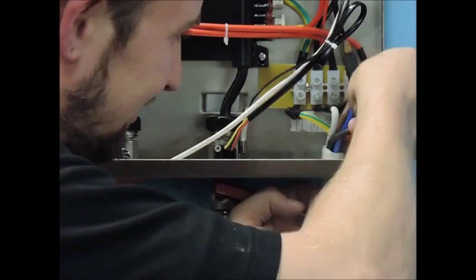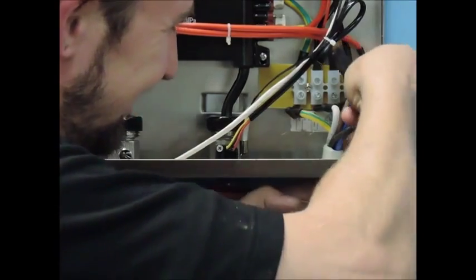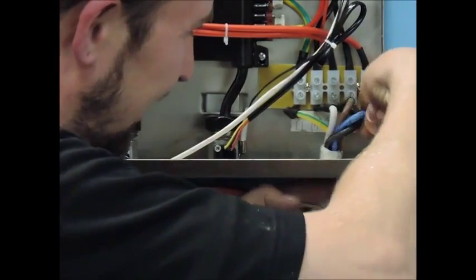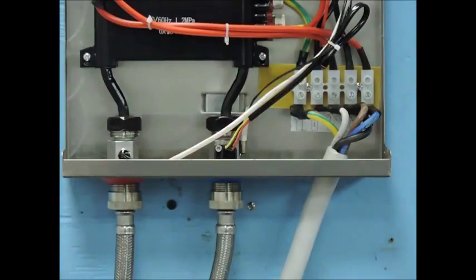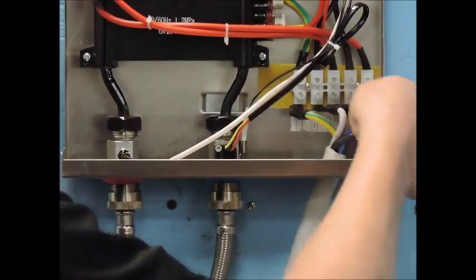Next, we have our first pair of power connections, and in our example, it will be the white and brown wires going into the first L1 and L2 terminals. These two wires will terminate at the same 50A double pole breaker for this model.